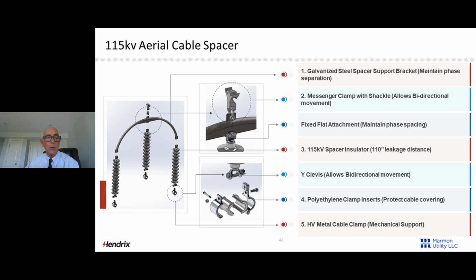Here's some of the components. Don't want to get too down into the weeds. We're using a galvanized steel support bracket to maintain the separation. We're holding heavier phase conductors, and there are longer spans between the spacers, so they will be forced to hold more weight. We're using a messenger clamp with a shackle. A Y clevis allows bidirectional movement. We're using polyethylene clamp inserts between the spacer clamp and the cable itself to protect the cable covering and give us a higher BIL. And we're using a high voltage metal cable clamp for mechanical support. So that's what that spacer looks like.